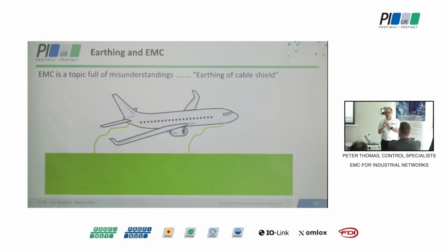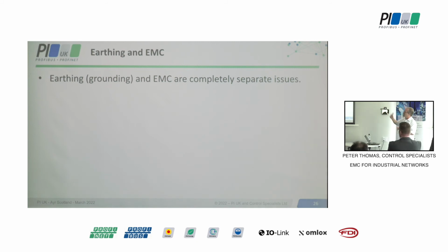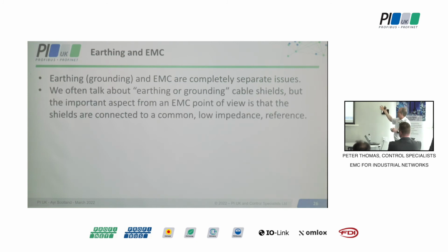But the terminology is, we should terminate the shield, and I know this will be contentious for some of you, we terminate the shield at both ends to a common reference. Now you might think I'm just saying it for the sake of it, but a common reference means a piece of metalwork where, in theory, there is no potential difference between the two ends. That's what a common reference is. But let's move further. Earthing and grounding and EMC are completely separate issues. We talk about earthing or grounding cable shields, but the important aspect from an EMC point of view is that the shields are connected to a common low impedance reference.